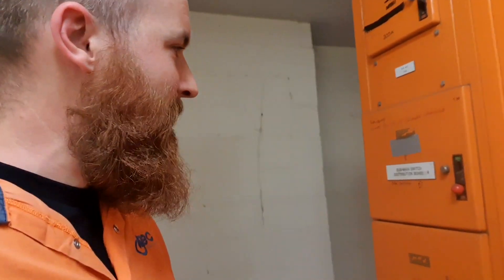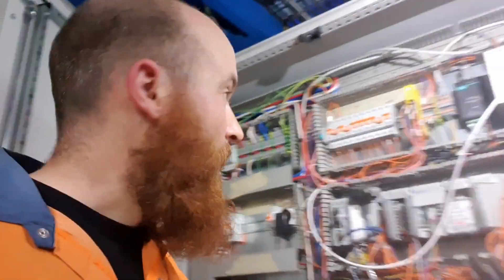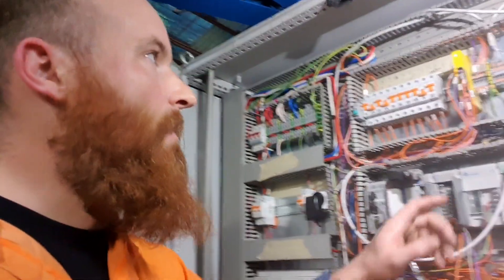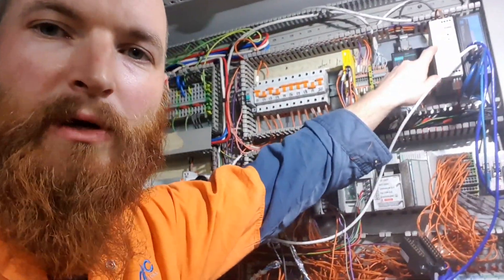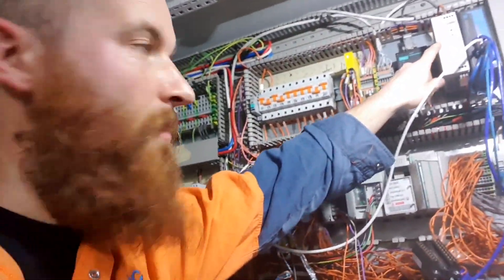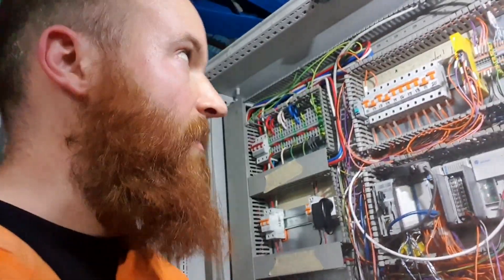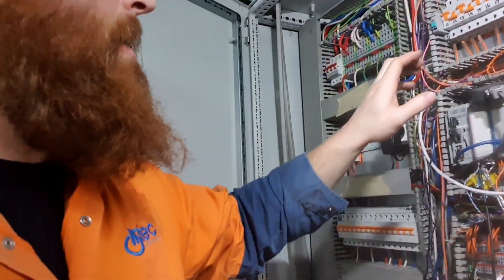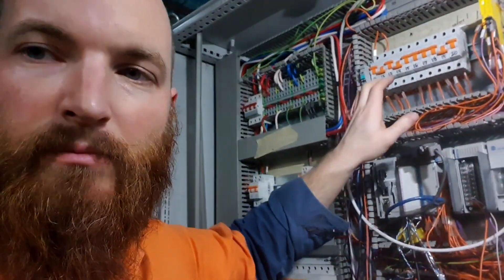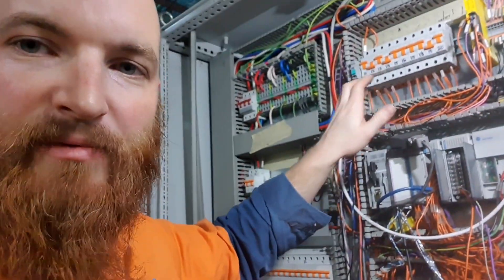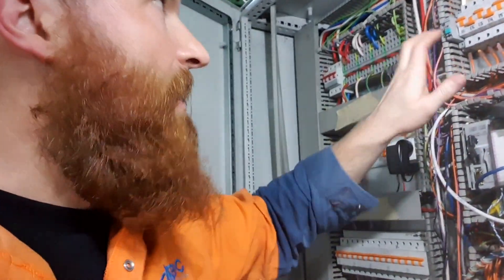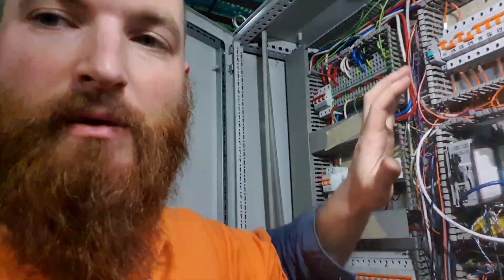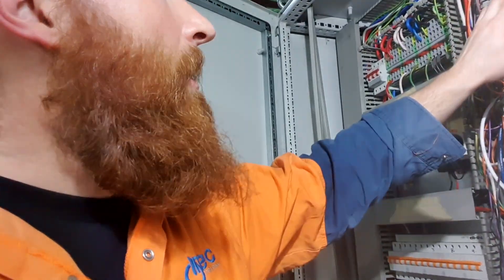Been looking for a panel supply for a big conveyor system. Right, so the start of this callout was the power supply here was dropping out. We're losing comms with the PLC. It's a bit of a mess. I isolated a bunch of stuff to try and get the power supply working. It was starting to perk back up, but then we're having troubles.